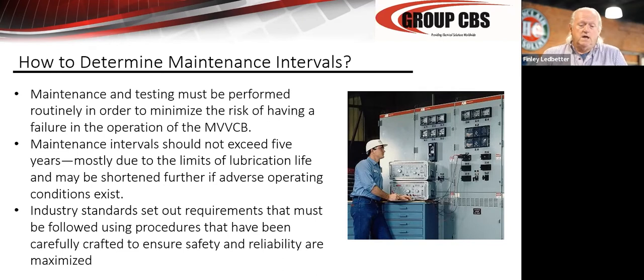Don't think it's not. In the NETA maintenance test procedures, the MTS, there are charts and ways to determine various pieces of equipment and what NETA recommends for annual, biannual, every 5-year maintenance, that sort of thing. The best thing I can do is offer that to you. I do have a paper on maintenance. There are a lot of them out there. If you go and search through the Doble, NETA, and IEEE papers on electrical maintenance procedures, I think you have to consider the risk of losing a particular circuit. Certainly, there are financial factors. In fact, how much money will the plant or your boss allow you to spend on the breaker? It's something we probably have to take offline here because it's a topic that would consume the entire hour.